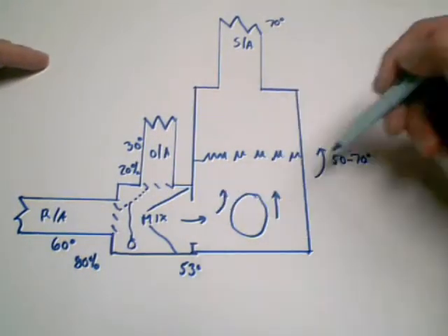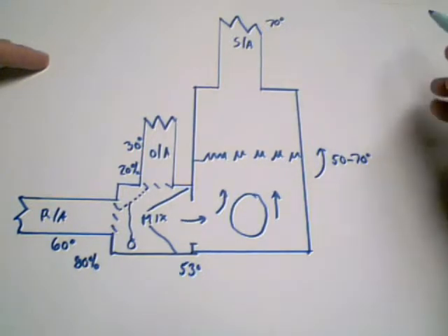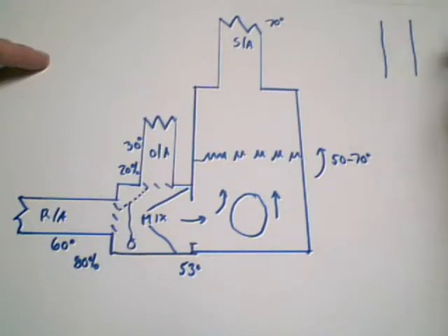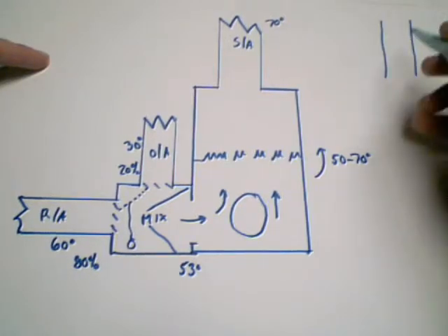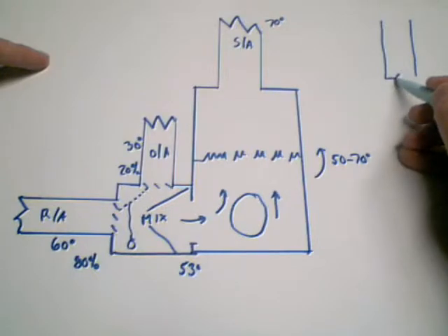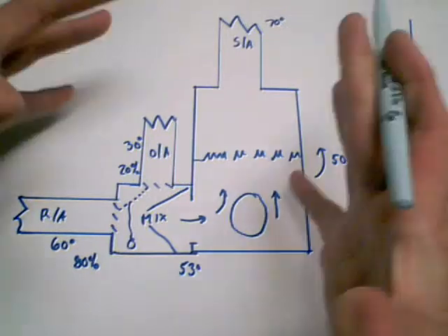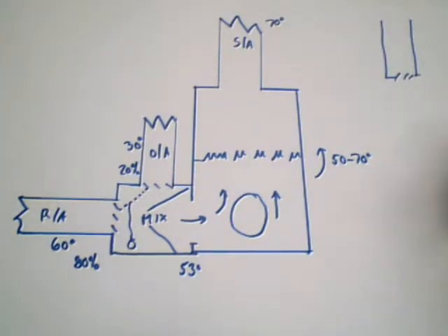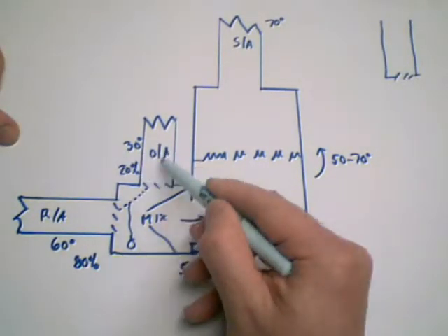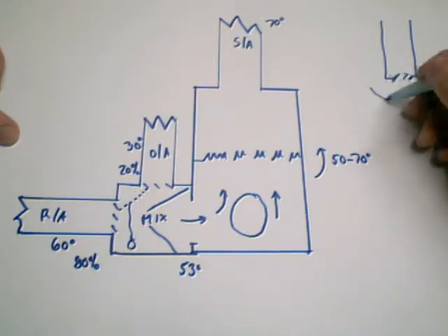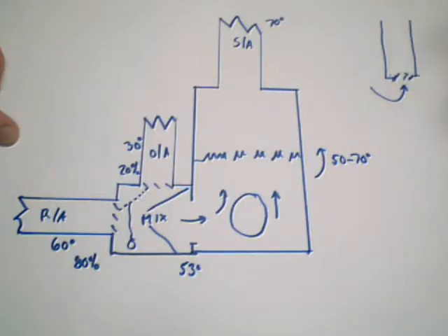The other thing that you don't see here is a relief damper or a relief ducting system. So out here, also just going to the outside air, is a damper system. And if we're bringing in outside air, the building pressure is going to increase. So that air has to go someplace. So whatever air is coming in here from outside needs to go back outside somewhere else. So elsewhere in the building, there's going to be a shaft here that opens, and then the pressure of the building just causes that air to discharge outside.